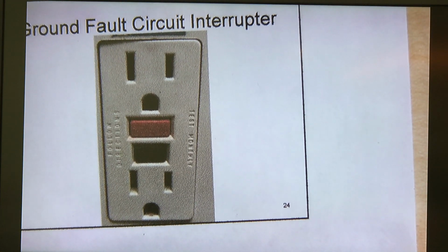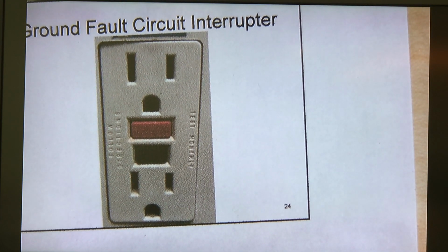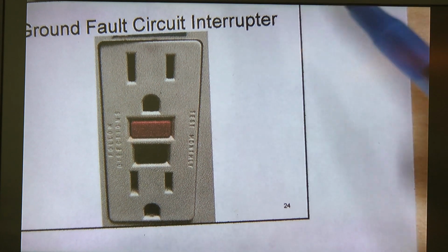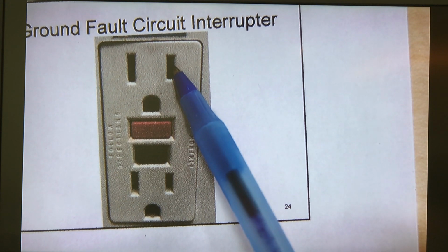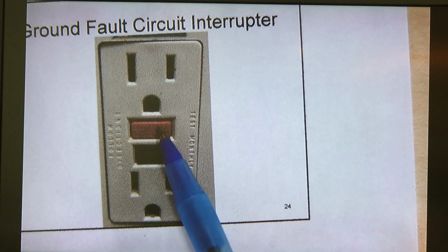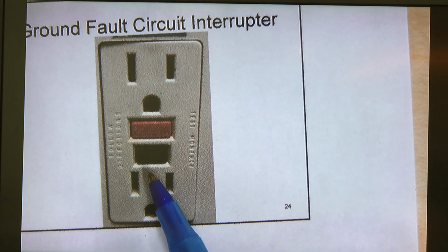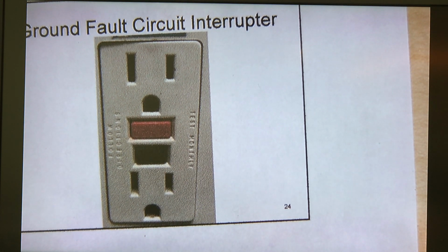What do they look like? Well, in this case, this is a shot taken right off by the sink in the bathroom. Notice that it's the same face, hot lead, longer neutral, ground. The difference here is that you have 2 little buttons, one of which is labeled test, which is just there to make sure that the device is working. Push the test button, it should pop off, it should trip. And then the other one is a reset. So you have a way to check it. Now that's meant for permanent installations.